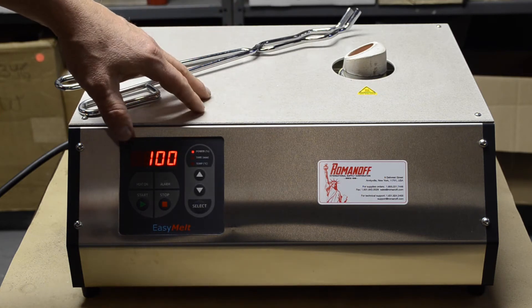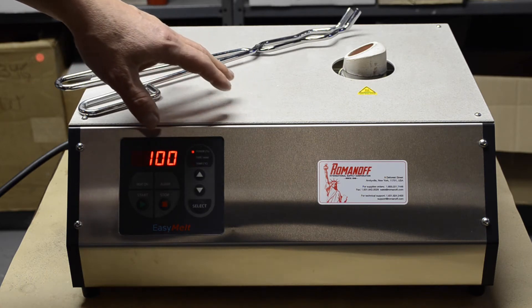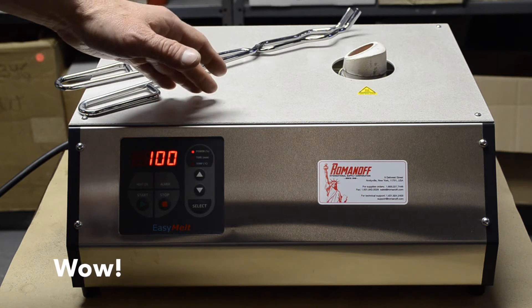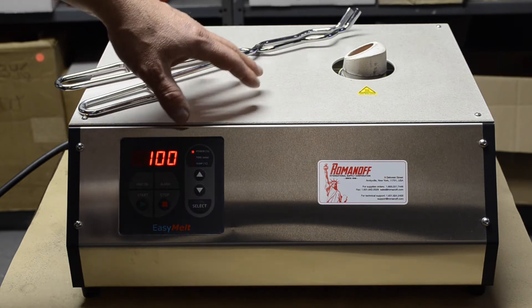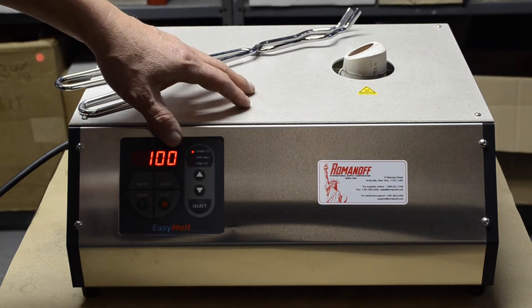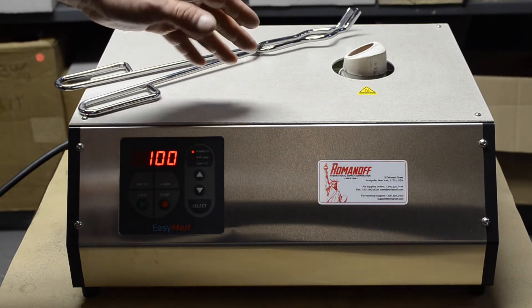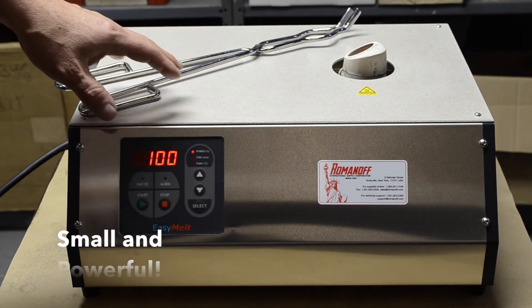And then we have this unit right here, which is made for higher temperatures up to 2000 degrees, which will melt anywhere between 50 to 250 grams of platinum. The power requirements for these machines are 220 volt, single phase. The dimensions of the machines are 360 by 450 by 180 millimeters high and weigh approximately 14 kilos, about 31 pounds.